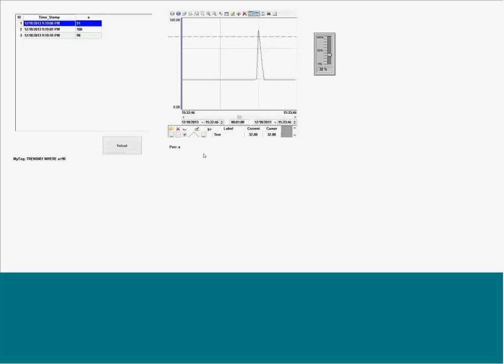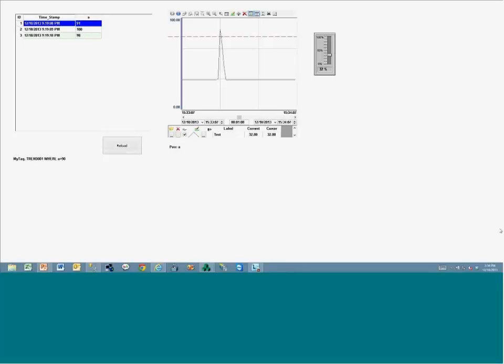So by using one indirect tag, you can dynamically point to any other tag in the whole application. You could have 10 million tags in the application. Using a string tag, you can point to any other tag in the whole application. And hopefully it addresses the particular question you had.